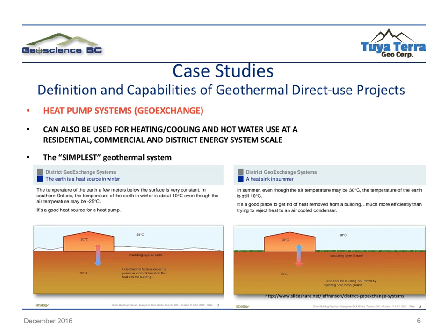You're using the constant temperature in the ground as a heat source for heating and hot water. Once you've got a GeoExchange system in place, this isn't necessarily useful if you're only using it for one residence, but if you've got a district heating system using GeoExchange, the efficiency can really be increased because you've interconnected different types of buildings with different heating and cooling loads. On top of using the ground as an energy source, you're also using all of the buildings connected within that system as a heat source or sink.